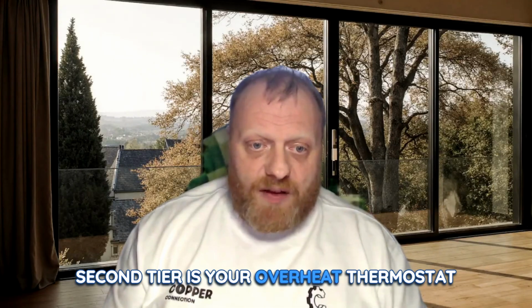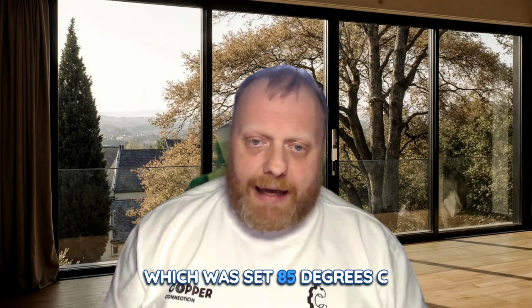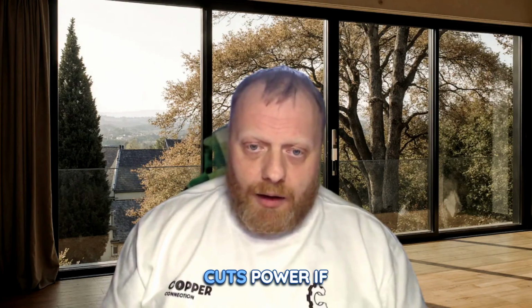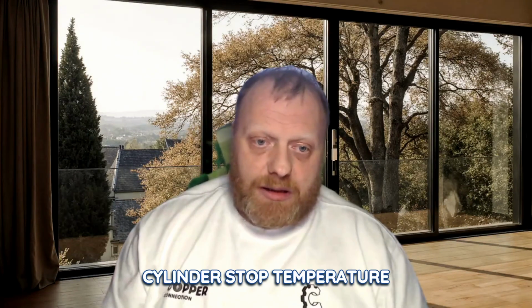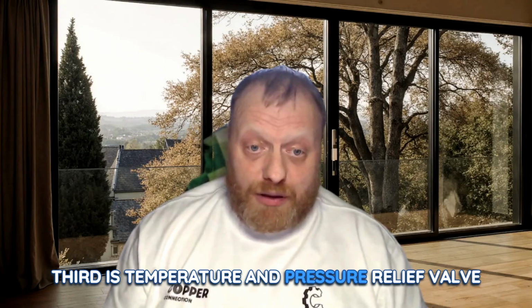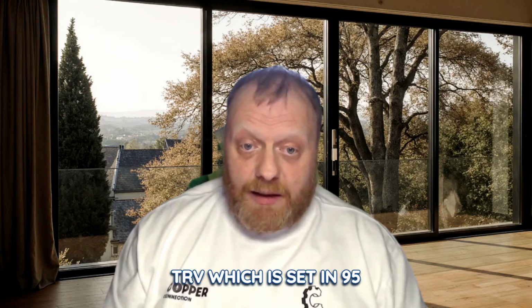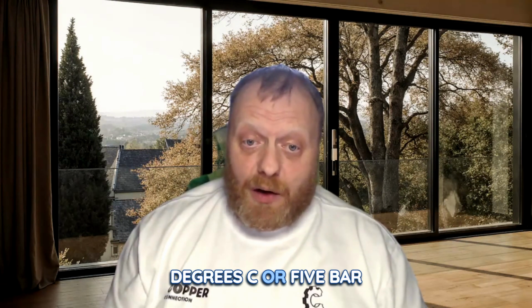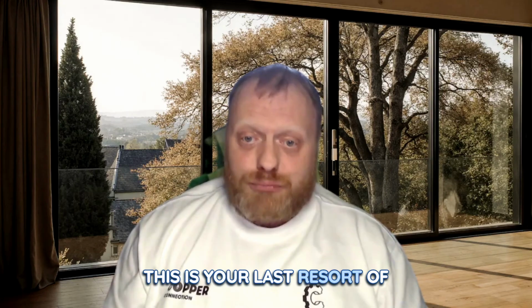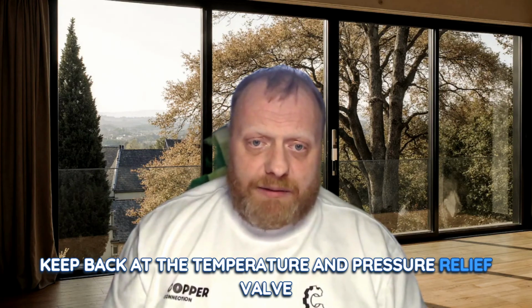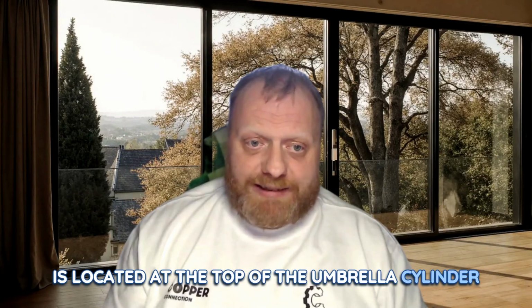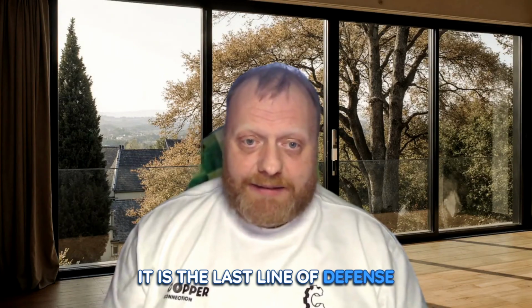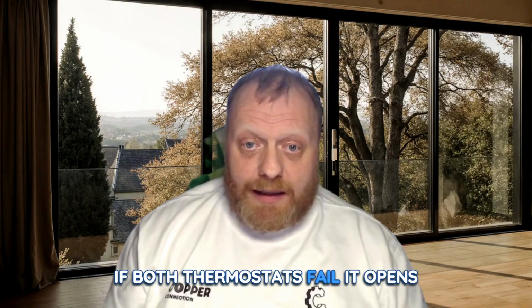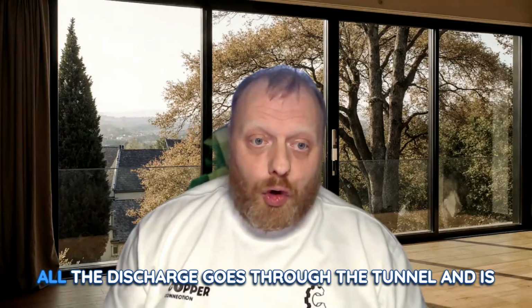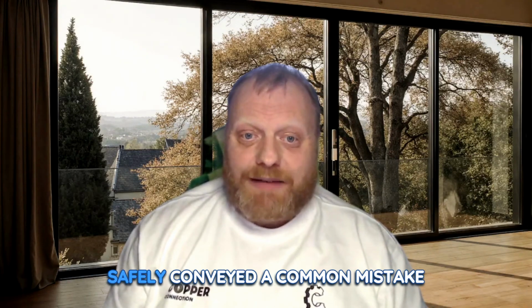Second tier is your overheat thermostat, which we set at 85 degrees C, cuts power if the cylinder stat fails. Third is the temperature and pressure relief valve, TPRV, which is set at 95 degrees C or 5 bar. This is the last resort of your safety devices. Key fact: the temperature and pressure relief valve is located at the top of the unvented cylinder. It is the last line of defence. If both thermostats fail, it opens and empties the cylinder. All the discharge goes through the tundish and is safely conveyed away.